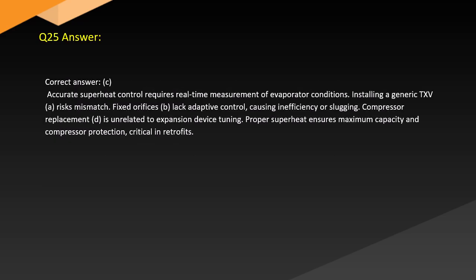Answer. Correct answer. C. Accurate superheat control requires real-time measurement of evaporator conditions. Installing a generic TXV, A, risks mismatch. Fixed orifices, B, lack adaptive control, causing inefficiency or slugging. Compressor replacement, D, is unrelated to expansion device tuning. Proper superheat ensures maximum capacity and compressor protection, critical in retrofits.